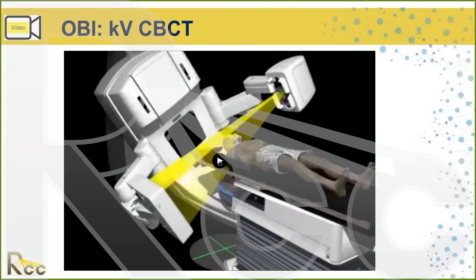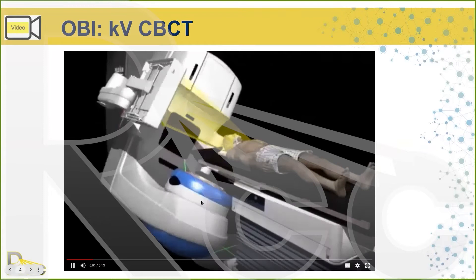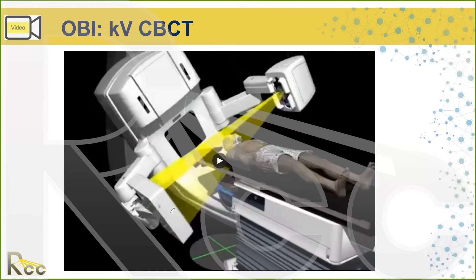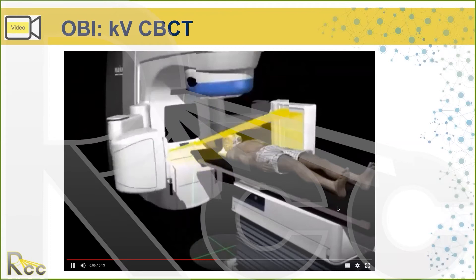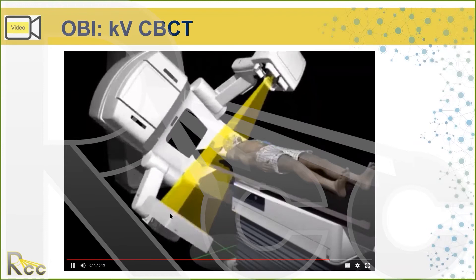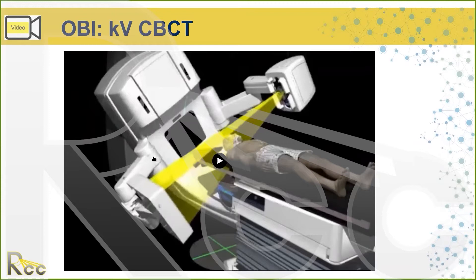Here's a picture of a cone beam on a linear accelerator. As the linear accelerator comes around the patient, you have an x-ray tube, a patient, and a flat panel detector. In a regular CT there's an x-ray tube and panel but only a narrow slit is allowed through, giving better resolution. With cone beam, they devised a way to attach this apparatus to the linear accelerator while retaining isocentric precision so you can put the patient in the treatment position and take a three-dimensional image of the patient's anatomy in real time — while the patient is on the table for treatment.